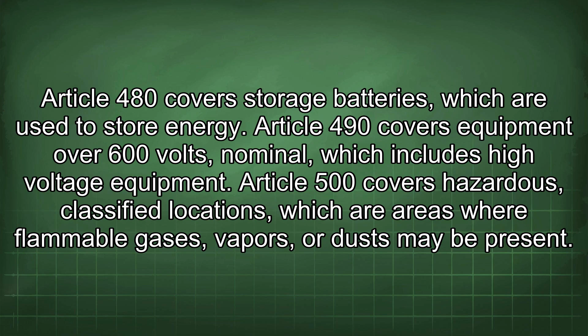Article 500 covers hazardous, classified locations, which are areas where flammable gases, vapors, or dust may be present. Article 501 covers Class 1 locations, which are hazardous locations where flammable gases or vapors may be present. Article 502 covers Class 2 locations, which are hazardous locations where combustible dust may be present. Article 503 covers Class 3 locations, which are hazardous locations where ignitable fibers or flyings may be present. Article 504 covers intrinsically safe systems, which are electrical systems that are designed to be safe for use in hazardous locations. Article 505 covers zone classification, which is an alternative method of classifying hazardous locations.